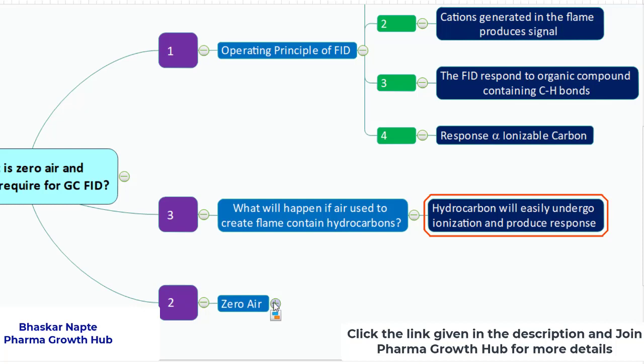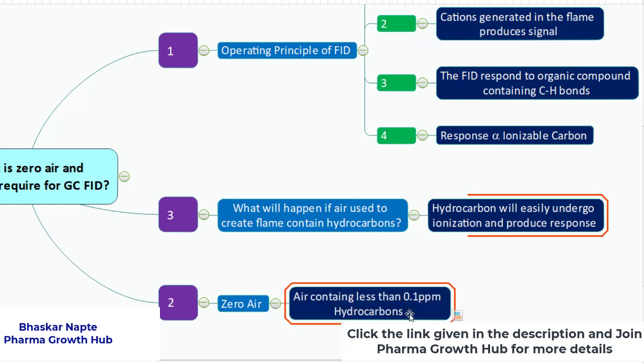Now practically, is it possible to have air with zero hydrocarbons? May not. And hence there is a limit given to it. Air containing less than 0.1 ppm hydrocarbons is called zero air.